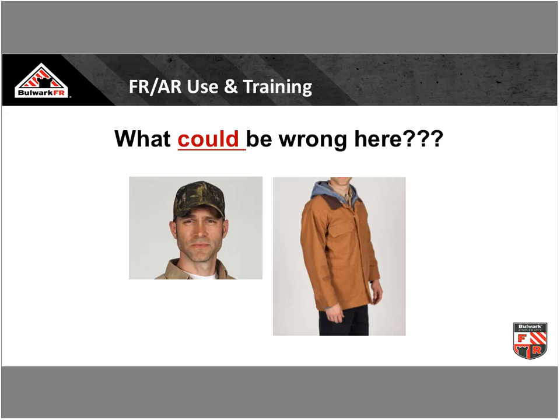Little things that folks don't normally think about. What do you put on your head? You have a perfectly sound flame-resistant arc-rated clothing program, and it's hot or it's cold or I'm sweating, and I put something underneath that hard hat or on top of my head that does not have the same flame-resistant properties, I have just jeopardized that whole program. That thermal event may ignite that, worst case, melt it to my head. Our brain is very, very sensitive when it comes to increases of heat, and if I melt something to my scalp, a very, very nasty outcome can happen there.